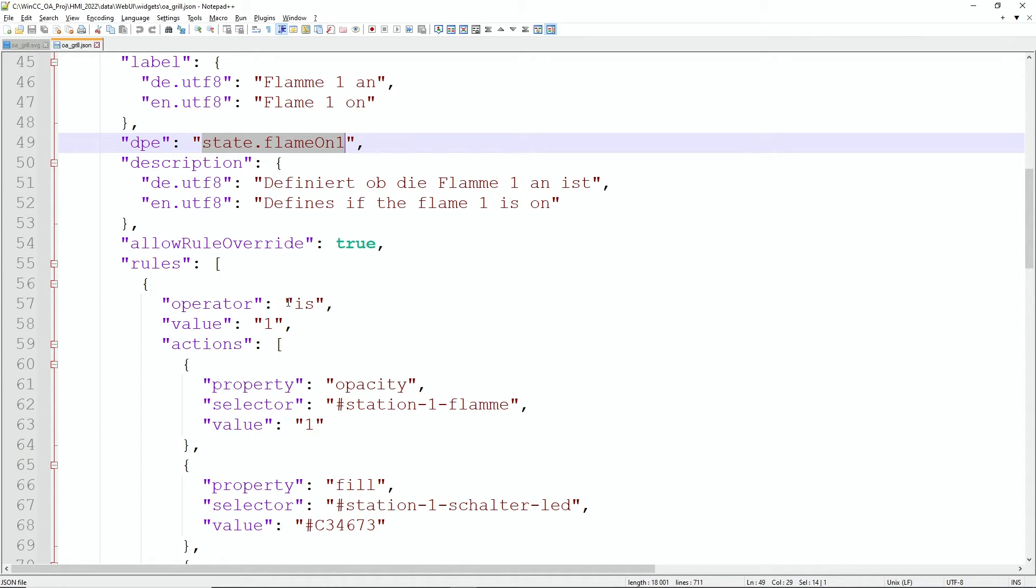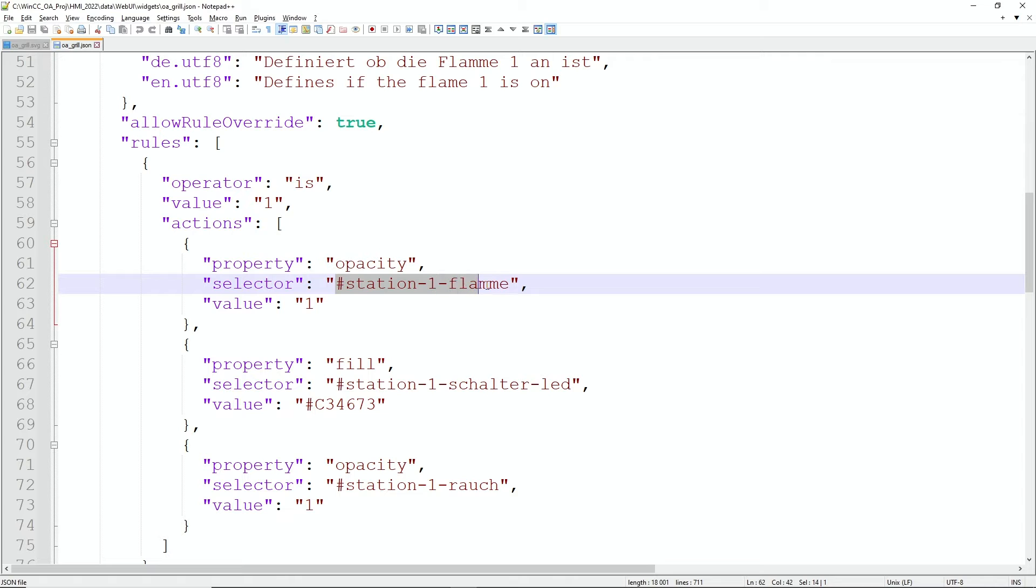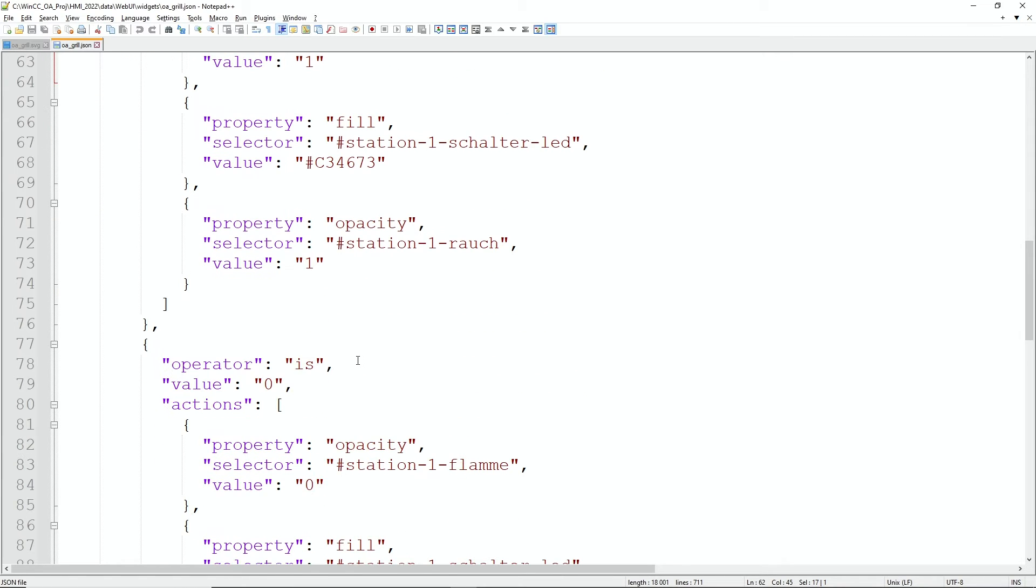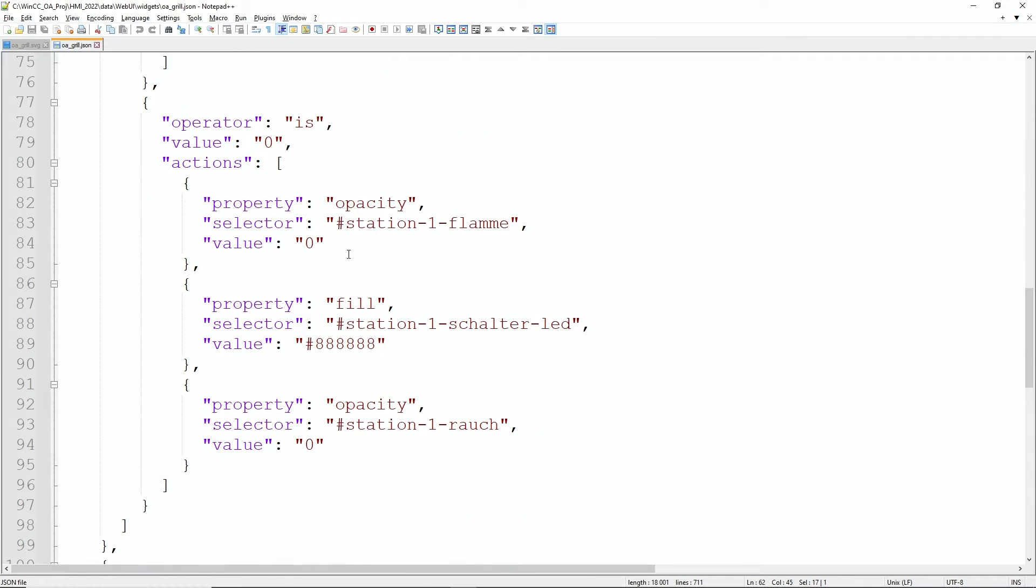It can have the value of 1 or 0, it's a boolean signal, and we have now two rules. One rule—if the operator is 1, we set the opacity of the station 1 flame (that is the ID from the SVG graphic) to the value true. Also we change the color and we set some other things to true. And when the operator is false then opacity is set back to false.